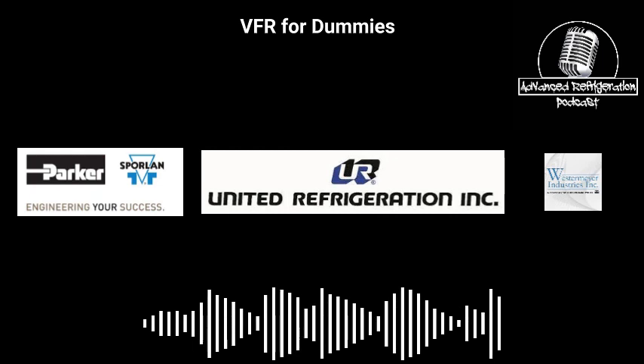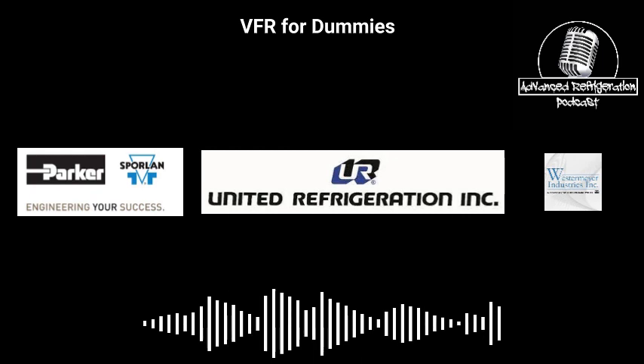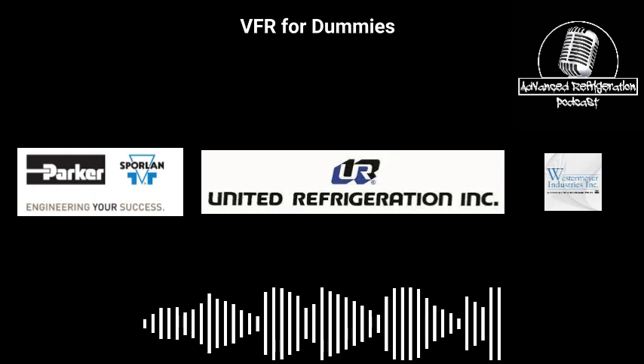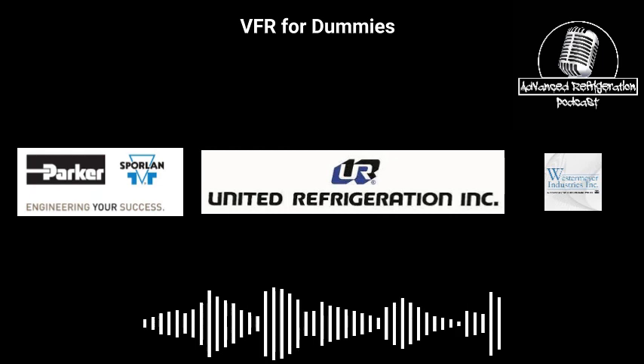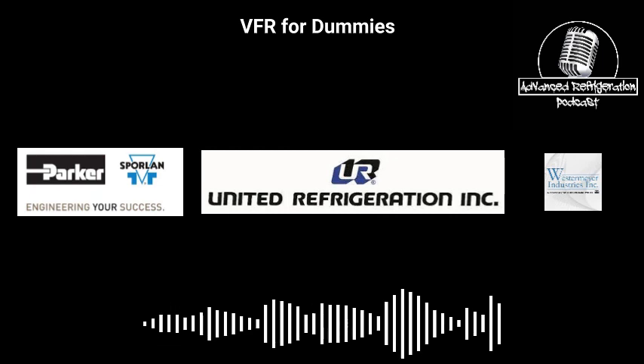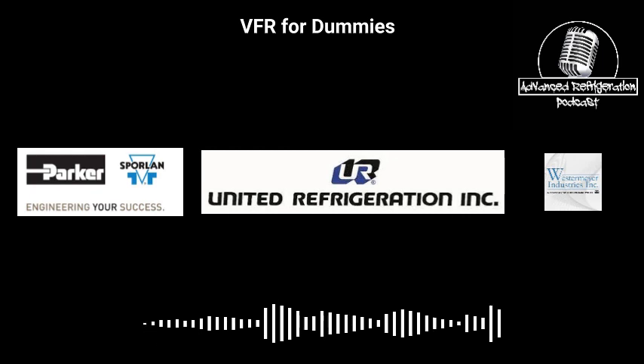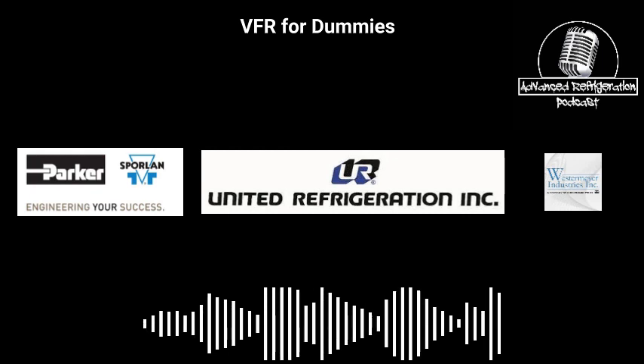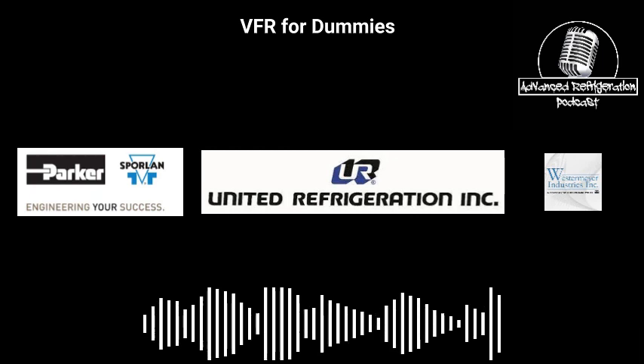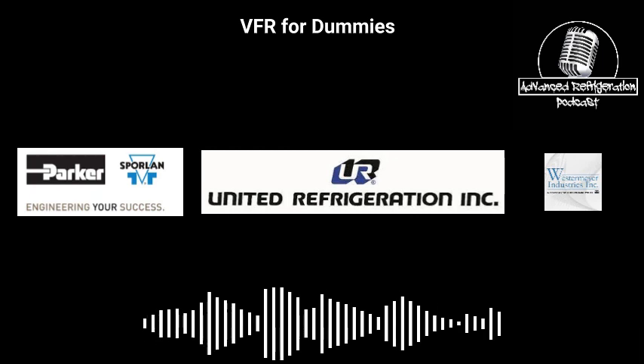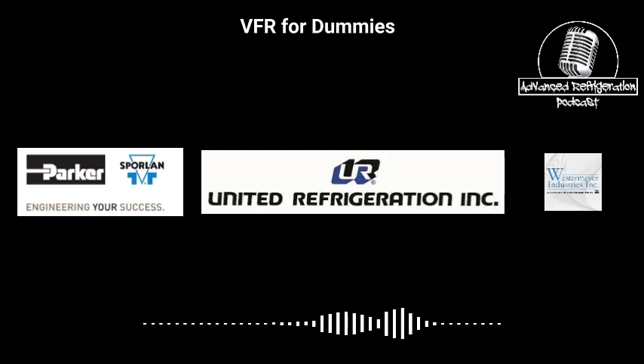Sorry, go ahead. No, one of the questions I had, since you talked about compressors: I've always thought, are they doing just a suction control, and that's what they're controlling the variable speed off of? They have a suction pressure set point bandwidth they're trying to maintain? It depends on the mode of the system. Some of it will control to suction superheat, yeah. It gets a little more in depth than that, depending on how big the system is. In a 3-module system with heat recovery, we have up to 6 individual outdoor coils. So it depends.